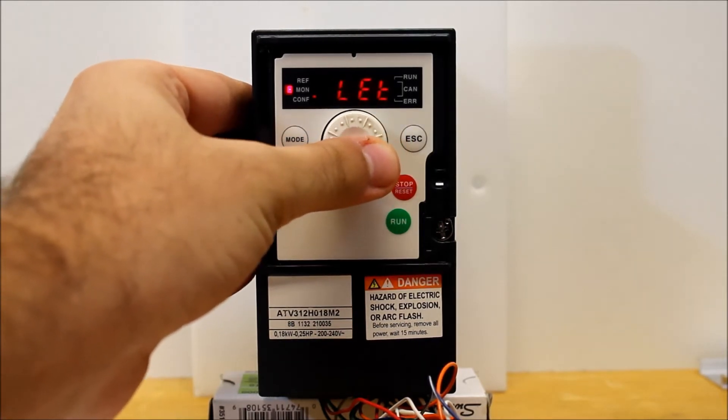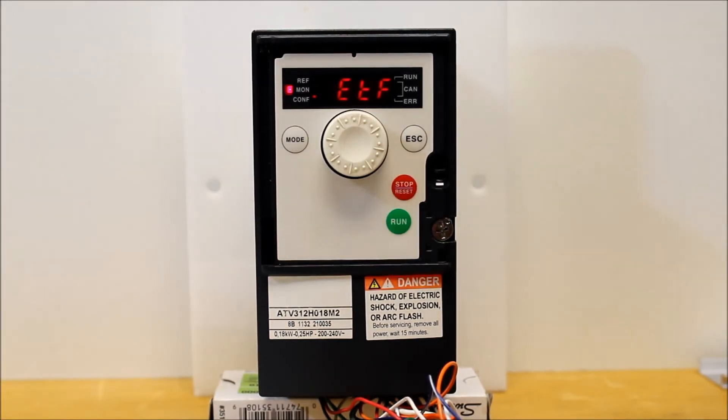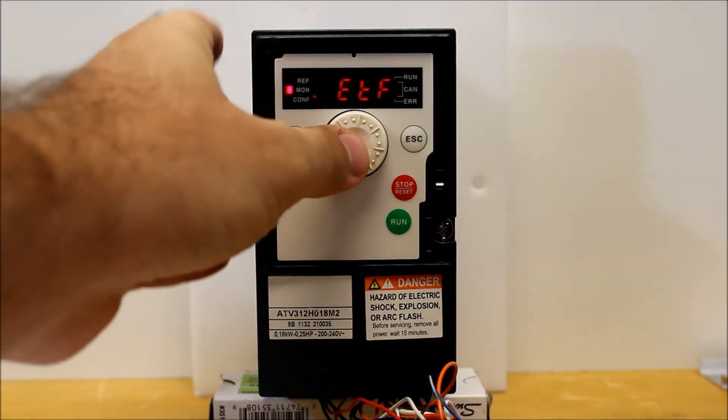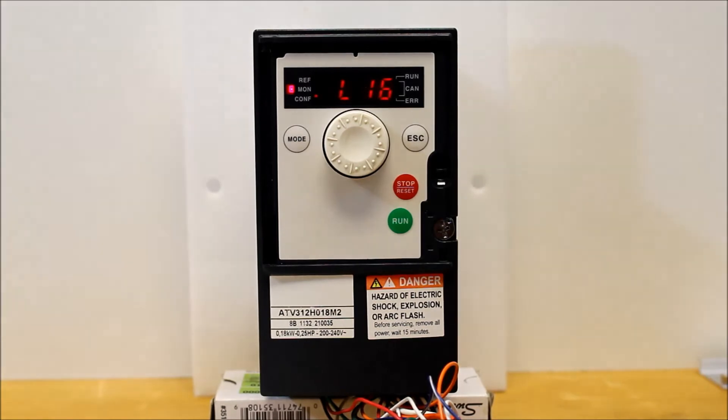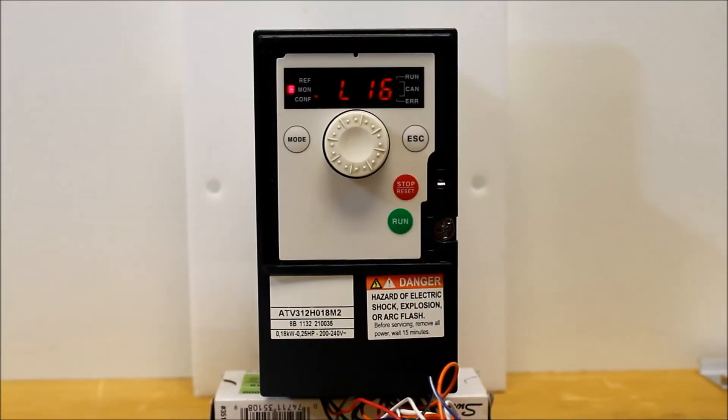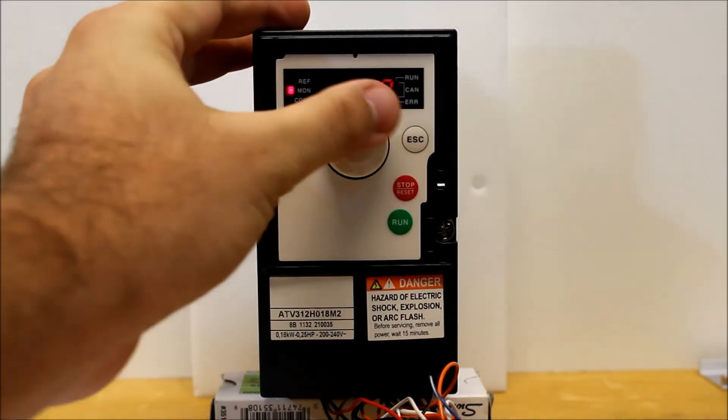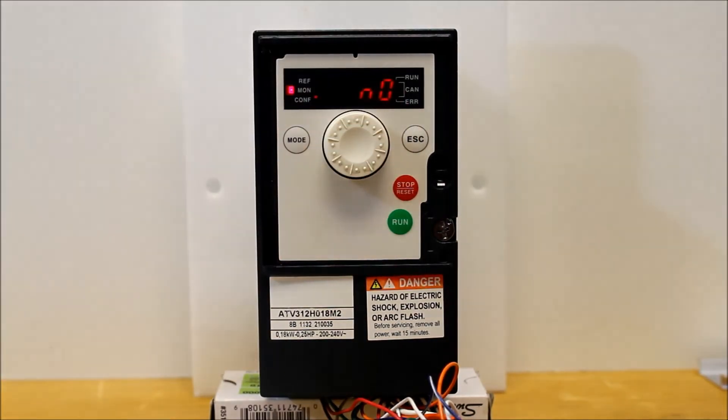Now you have to find the ETF parameter. This is your external fault, enter. Now from the factory, this is not programmed to any logic input. It's actually assigned to no, but we can go ahead and assign to whatever you want.